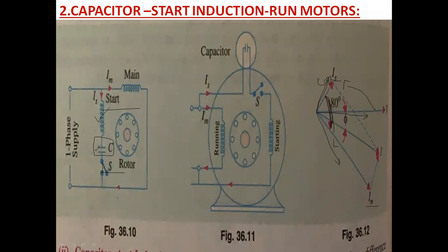Okay, and this capacitor, what we are discussing, is designed for short duty services only. It should not be used more than 20 operations per hour, and each operation delay time should be at least 3 seconds, more than 3 seconds.